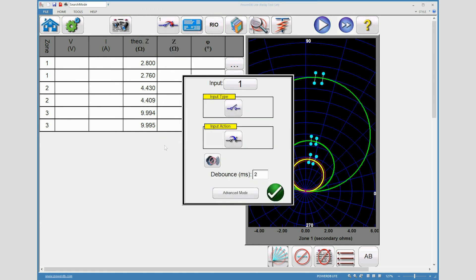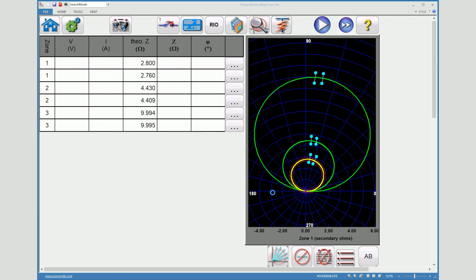So if I come to the binary input, I will select inputs. And now I have the option to decide which input I'm going to use. So whichever one I have wired up to my test set. So I have number one. Is it a dry contact or normally wetted contact? Or do I have an action that's going to be normally open or normally closed? Since we're coming out of the zone into the zone, we can do a normally open to closed action. And then we can select the check mark. Now we have our binary input configured. And now we can perform the test.